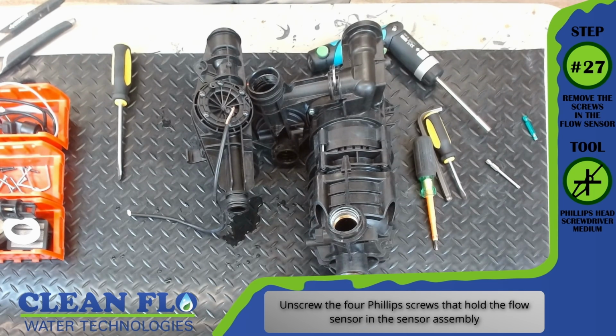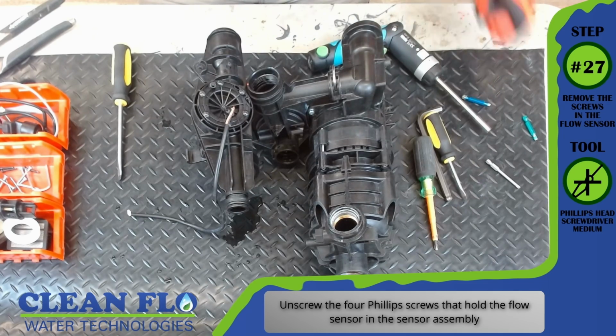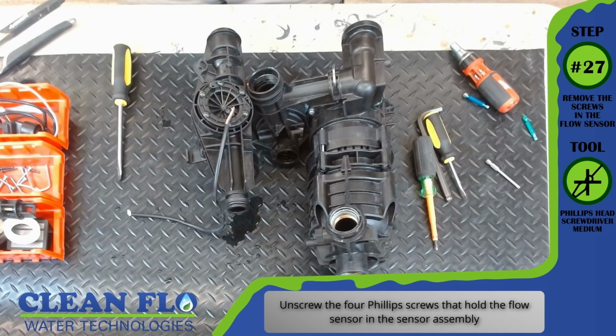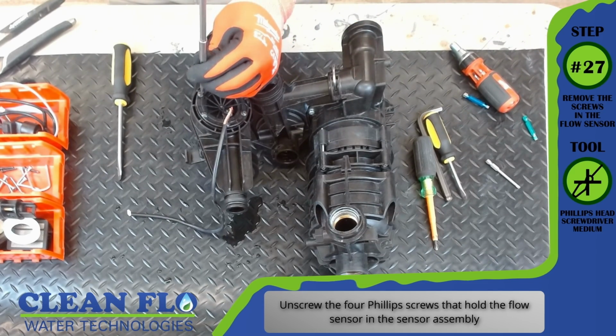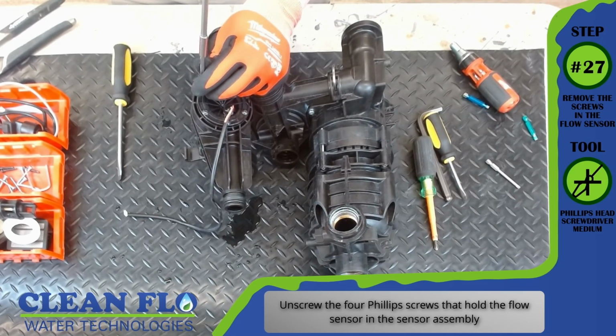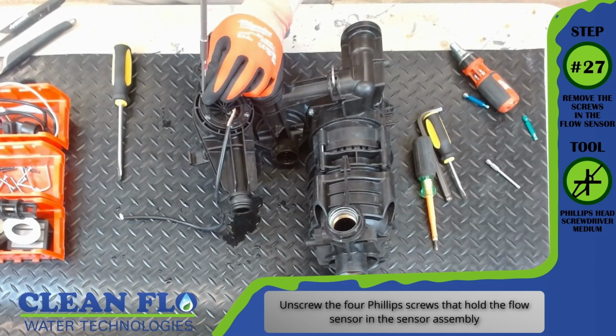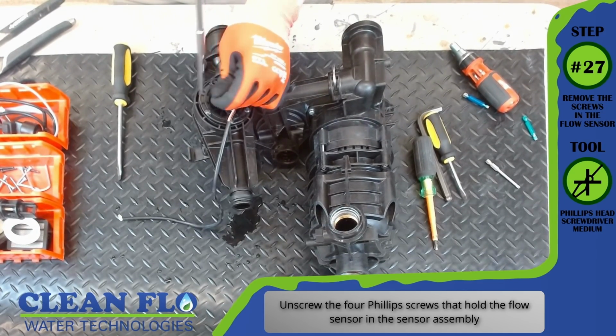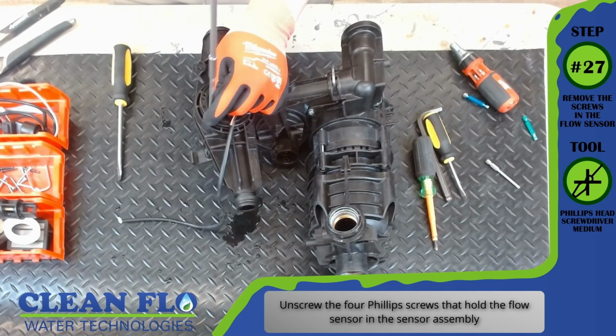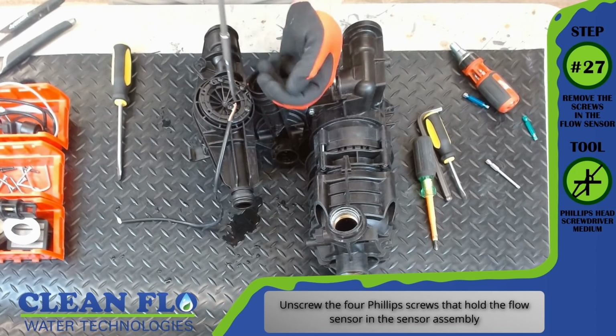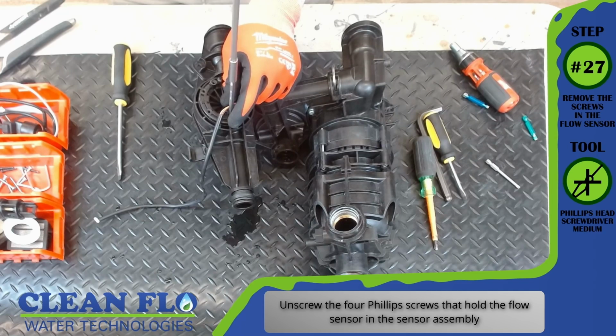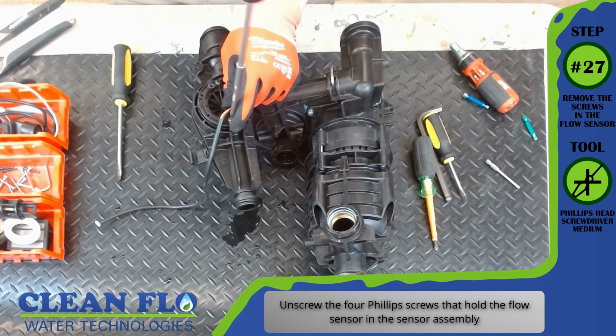The flow meter is located inside the flow meter assembly. It is a paddle wheel flow meter, so as the water flows by, the paddle wheel will spin, providing a sensor signal to indicate that there is flow. By removing these screws and opening up this enclosure, you can access the paddle wheel and make sure that everything is in proper operation.